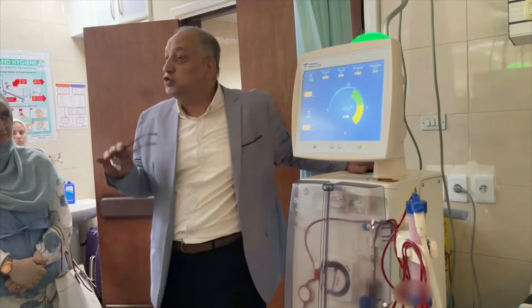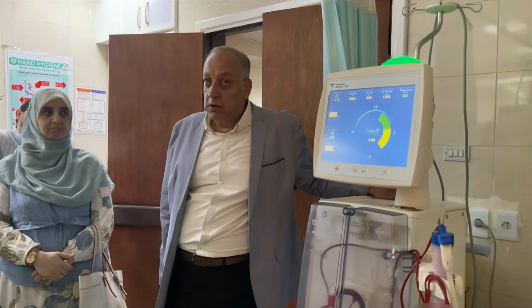After that, you have to consider the best hemodiafiltration machine. For example, on this machine, if you look at the back, you will find 2 endotoxin retention filters, and it's important to understand that they are in series, not in parallel. How many sessions is it enough for? It's 100 sessions or 3 months. And if you are using chlorine continuously for disinfection, the maximum is between 7 and 10 chlorine disinfection protocols. Remember that the machine tests, at the time of installing the endotoxin filter, the integrity of the fiber, that there is no leak in the filter, but it never tests the endotoxin capacity of the filter.